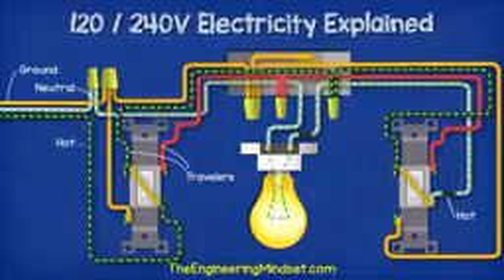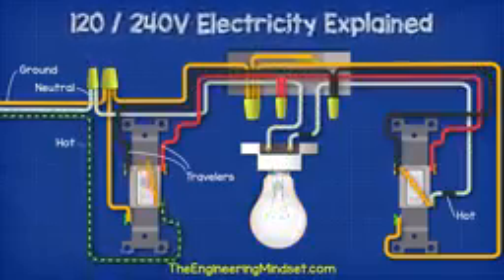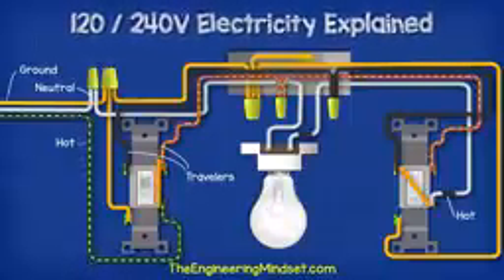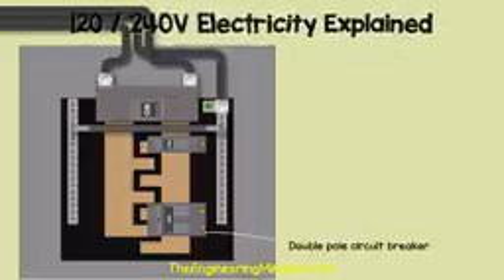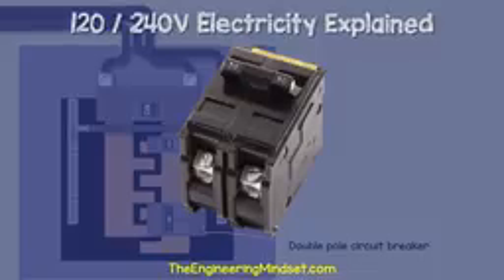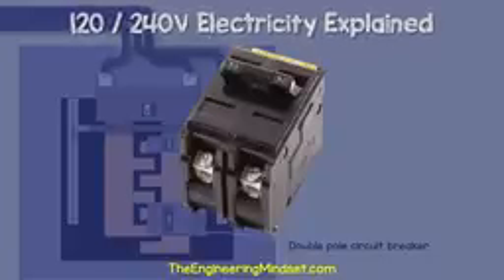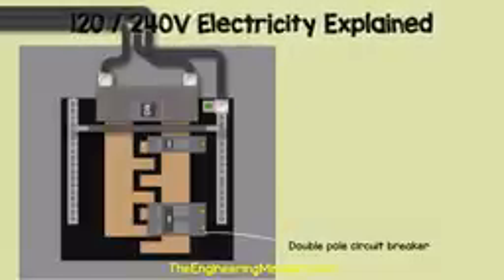We've covered lighting circuits in detail in a separate video. Do check that out, links in the video description below. Okay, so what else might we find here? Well, we might find a double pole circuit breaker, which will let us connect to both bus bars to get 240 volts, which we can use to power larger appliances like dryers, ranges, and air conditioning units.